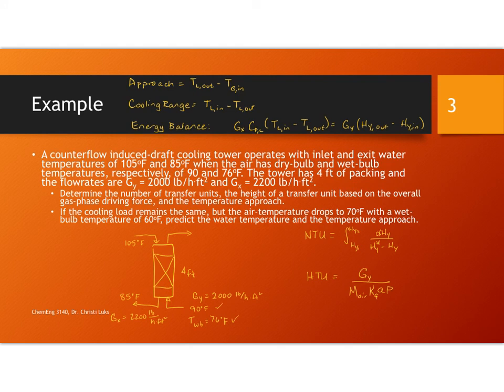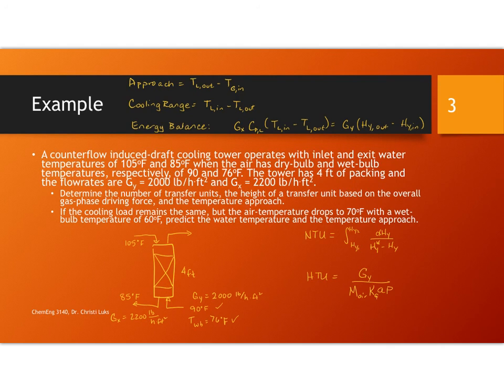Let's begin looking at the solution by first calculating the enthalpy of these airstreams. We have formulas in the book or you can look these up. The enthalpy of the gas coming in with a temperature of 90 degrees and a wet bulb temperature of 76 is 32.7 BTUs per pound mass. This is from the formula in section 10.5.